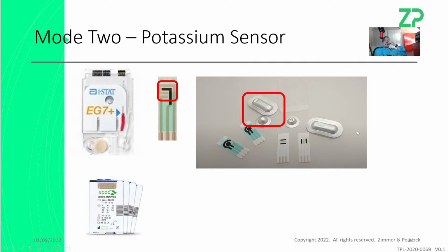And these sachets, I think, the original question a minute ago was, can you test whole blood? And the answer is you can, for example, the glucose sensor. But you have to make quite a good sensor and a very reproducible sensor in order to do that. If you're not able to do that, then you can start giving yourself a bit of a break by putting things like calibration solutions on there, or solutions that prepare the sample. That's kind of mode 2.